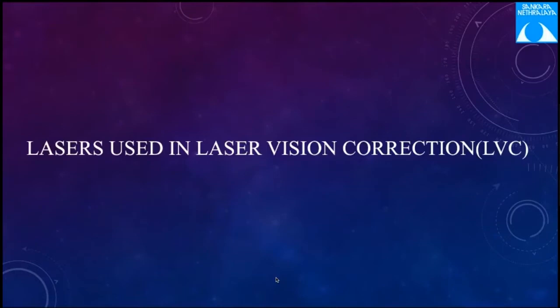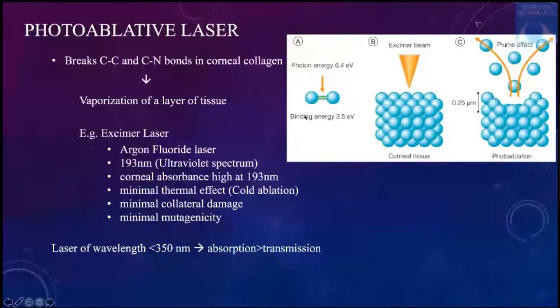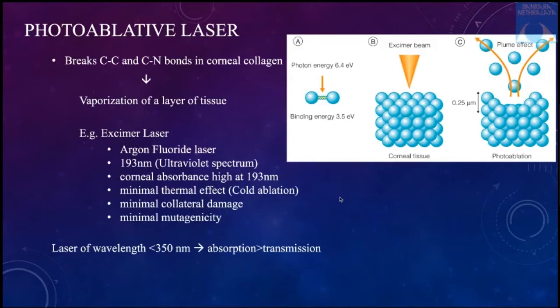The lasers used in laser vision correction include the photoablative laser. The excimer laser is an excited dimer in which electrical energy creates a dimer between argon and fluorine, which is highly unstable, breaks down, and releases photon energy of approximately 6 electron volts — greater than the binding energy between carbon-carbon and carbon-nitrogen bonds in corneal collagen — leading to ablation and vaporization of tissue creating the plume effect. Argon fluoride is used because at wavelengths less than 350 nm, absorption predominates. Corneal absorption is high at 193 nm, with minimal thermal effect and minimal collateral damage — hence called cold ablation.